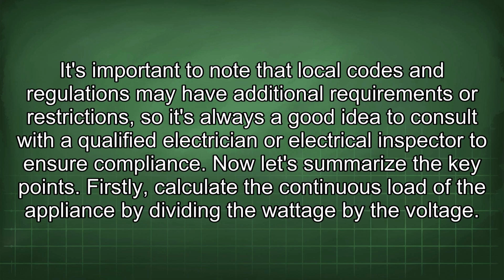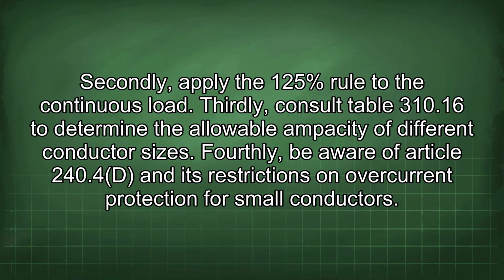It's important to note that local codes and regulations may have additional requirements or restrictions, so it's always a good idea to consult with a qualified electrician or electrical inspector to ensure compliance. Now let's summarize the key points. Firstly, calculate the continuous load of the appliance by dividing the wattage by the voltage. Secondly, apply the 125% rule to the continuous load. Thirdly, consult Table 310.16 to determine the allowable ampacity of different conductor sizes.